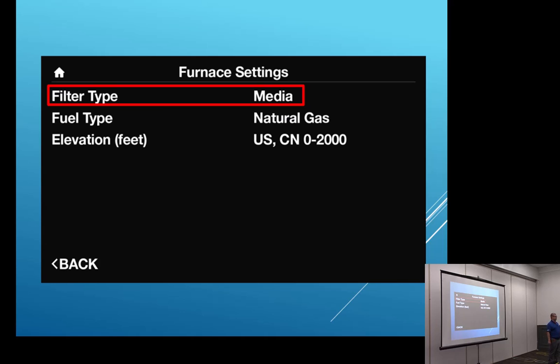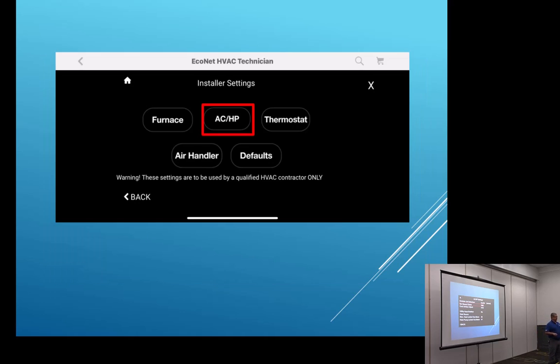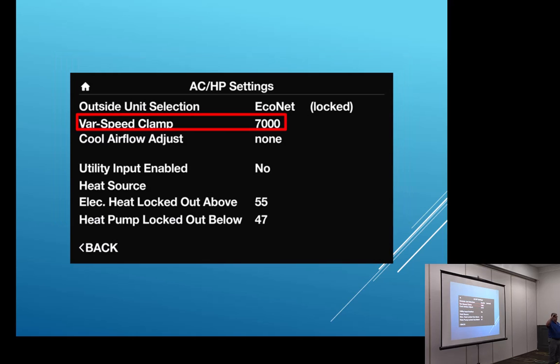You can put a media or electronic filter in here, select that. If you have propane, you want to select propane on here from natural gas. Also, if you do have propane, remember, you got to get a propane kit, change the orifices on the gas furnace and the spring inside the gas valve, okay? If you don't do that and you go back a few months later and you haven't changed any of that, and you go up to the house and you look at the flue pipe, if it hasn't caught on fire, it's black as that bag over there. And you go, oh my gosh, okay? That's what happened. So be careful with that.